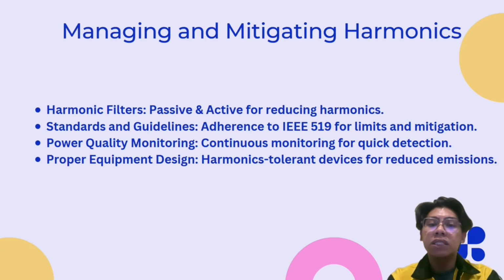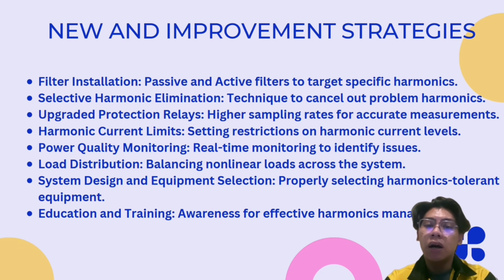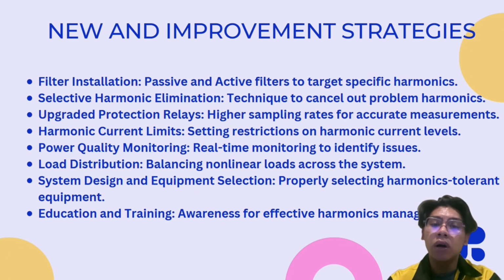And then the next part is managing and mitigating harmonics. For harmonic filters, there are two types, passive and active, for reducing the harmonics, and also the standards and guidelines, following adherence to the IEEE 519 for the limits and the mitigation. For power quality monitoring, continuous monitoring is used for quick detection, and for proper equipment design, harmonics tolerant devices to reduce the emissions. And for the new and improved strategies, the first strategy is filter installation, which will use passive and active filters to target specific harmonics.